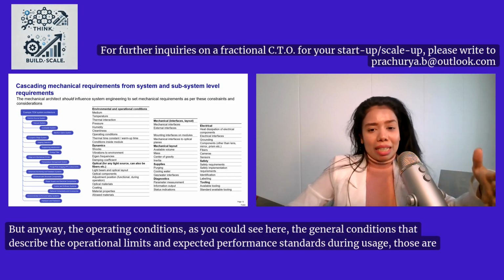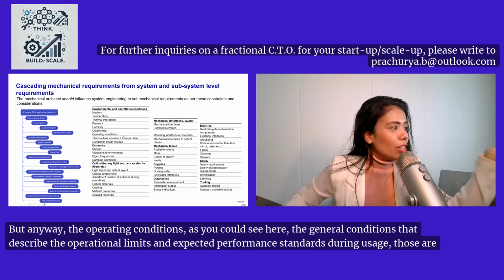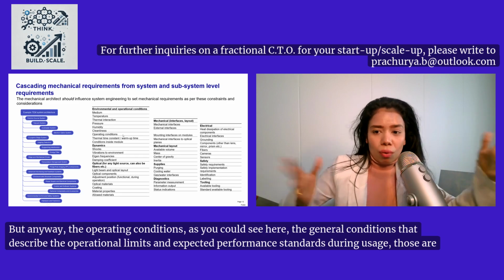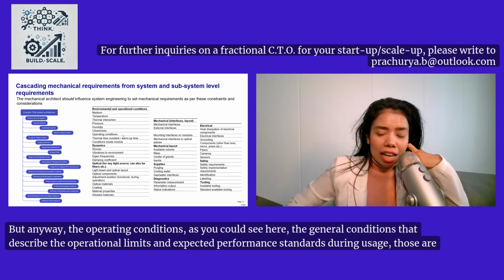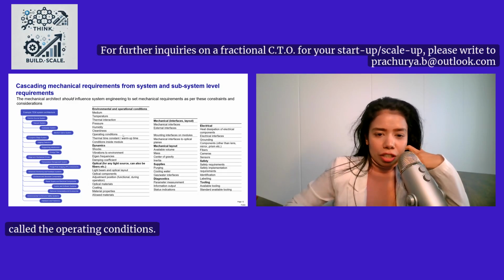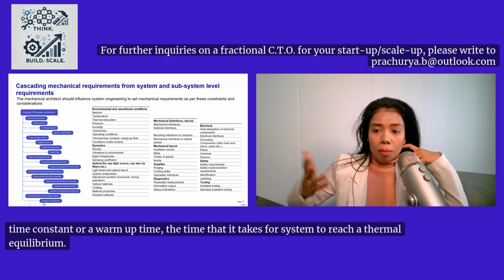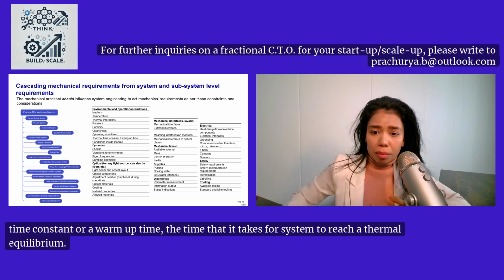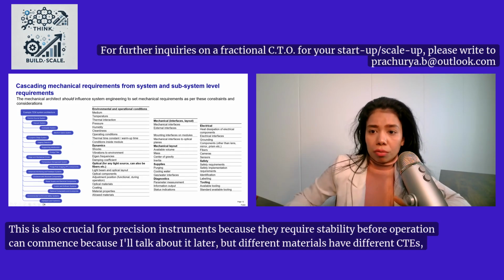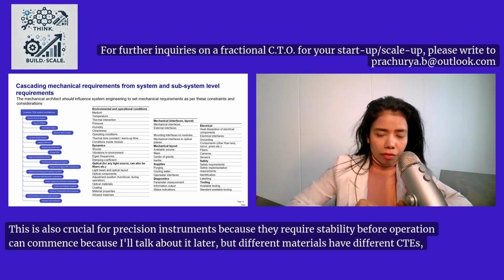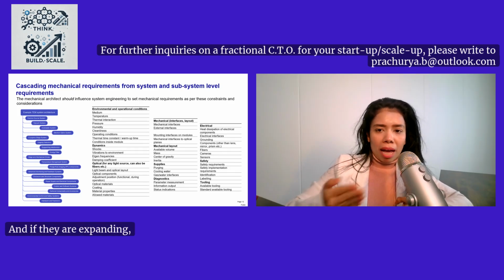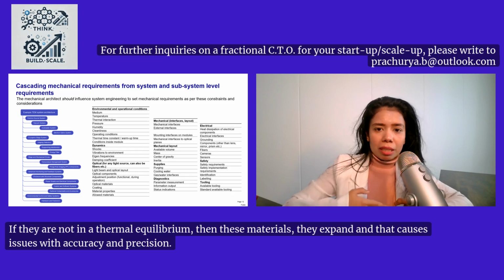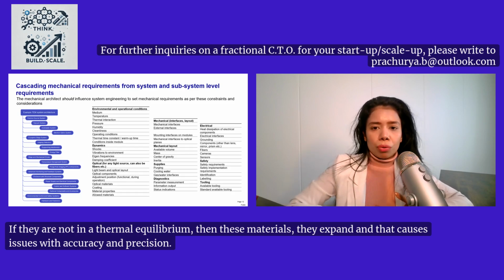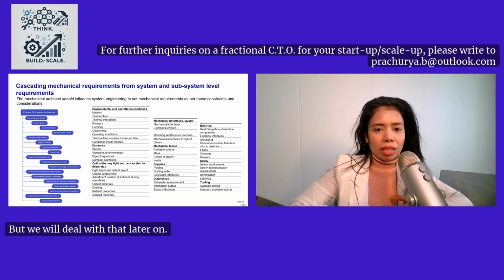But anyway, the operating conditions, as you could see here, the general conditions that describe the operational limits and expected performance standards during usage, those are called the operating conditions. You have your thermal time constant or a warm-up time, the time that it takes for the system to reach a thermal equilibrium. This is also crucial for precision instruments because they require stability before operation can commence. Because I'll talk about it later, but different materials have different CTEs, coefficients of thermal expansion. And if they are not in a thermal equilibrium, then these materials expand, and that causes issues with accuracy and precision. But we will deal with that later on.